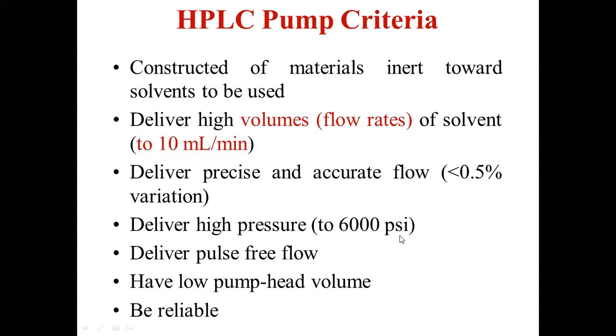After looking at the requirements, the pumps are of four types: reciprocating pumps, syringe pumps, constant pressure pumps, and pneumatic pumps. Reciprocating pumps, syringe pumps and even constant pressure pumps are the most used pumps in HPLC separation. Let us see one by one. A reciprocating pump will have 1, 2, or 3 pump heads. It is advantageous to have more heads because the pulses will be less. If the heads are more in a pump, the pulses will be less, so the pulse damping role will become minimal. And the head volume will be from 50 to 250 microliters only.